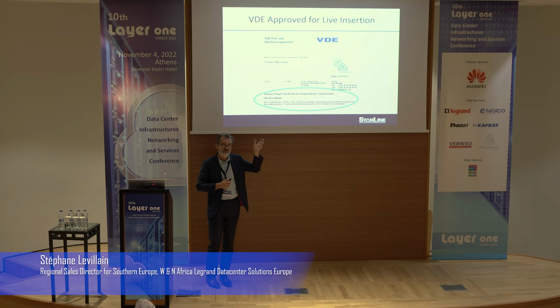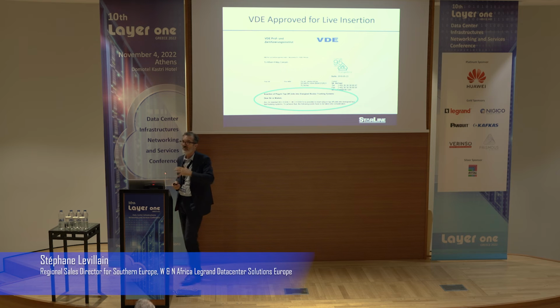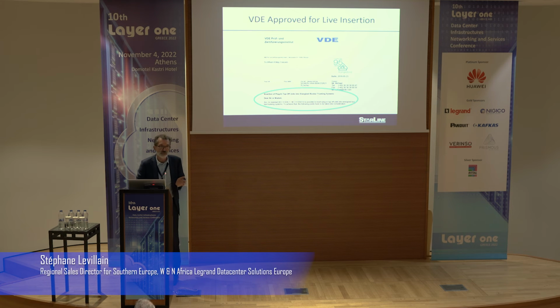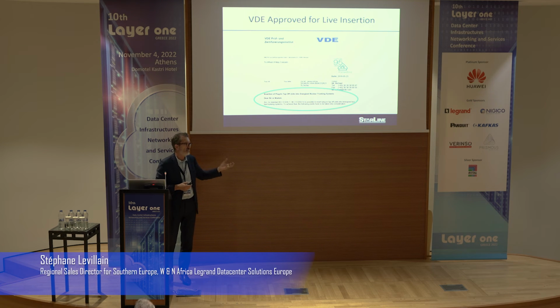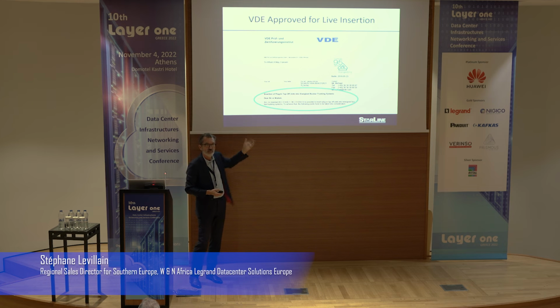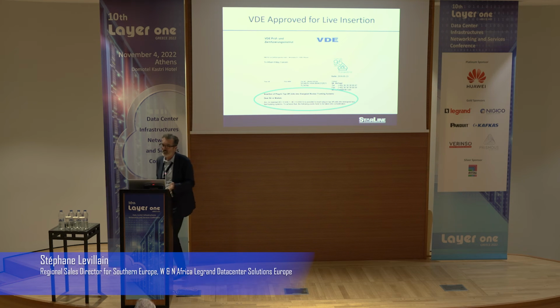VDE is stating that with the Starline solution, you are able, on an energized busway, to connect or disconnect the tap-off by yourself. This is a very important added value for the operation manager, because when you want new racks coming into your IT room, with the legacy cabling solution, you need to ask an electrical engineering company to come and make a quotation. It costs a lot of money. They will come perhaps in 1 week, 2 weeks. You have to wait. If you have your solution with busway, for new racks, you take your tap-off, insert the tap-off, you connect the racks, that's all. So it's very agile.